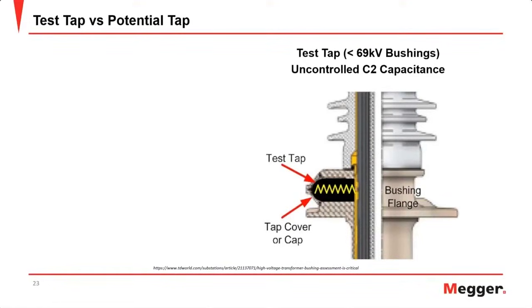And since it is uncontrolled, the capacitance would change in this way. What you may notice when you test these bushings hanging from a crane is that you will see the capacitance measurement change from the time that it is suspended to the time that it's actually installed in a transformer. Again, this is typically for bushings that are less than 69 kV.